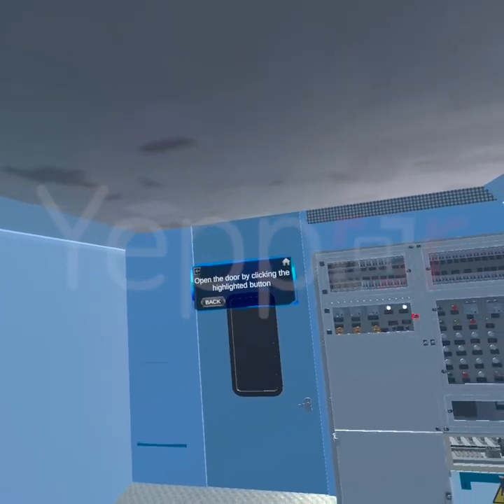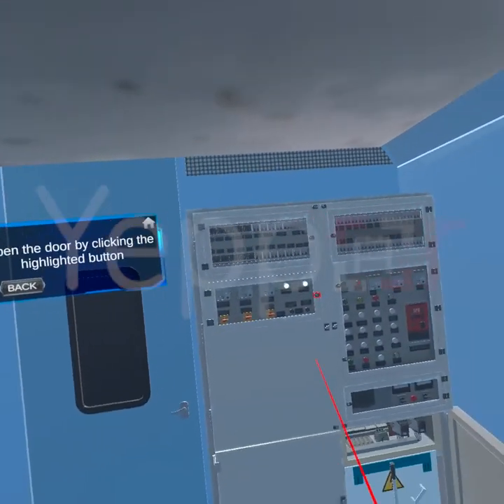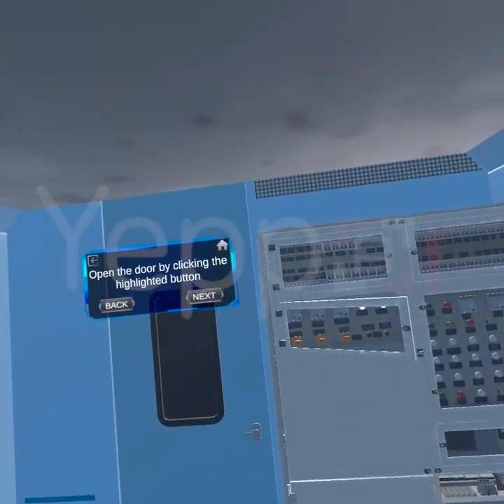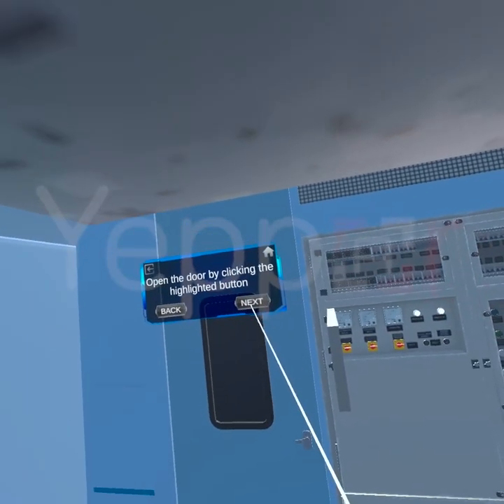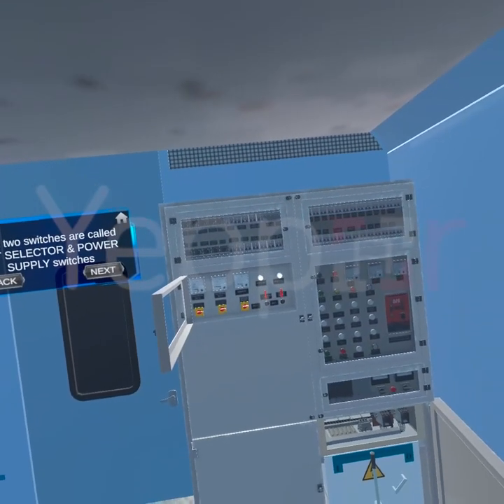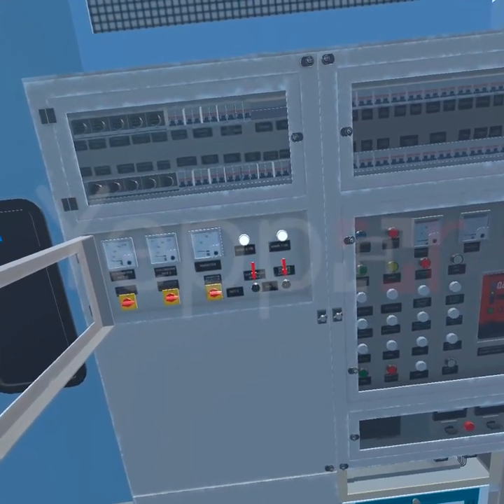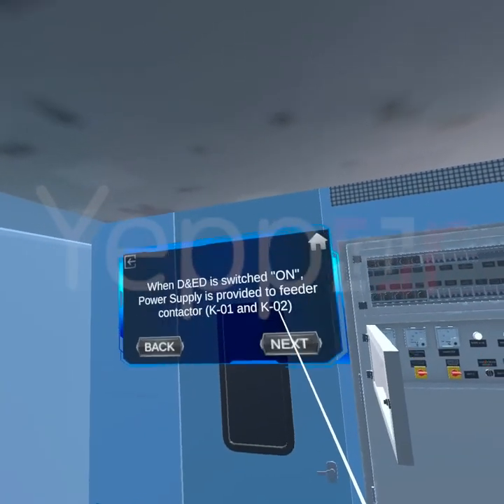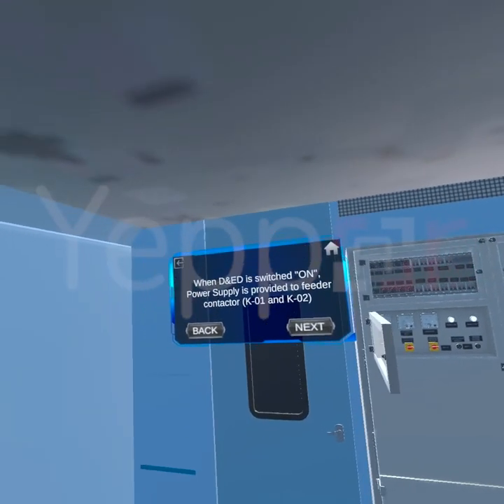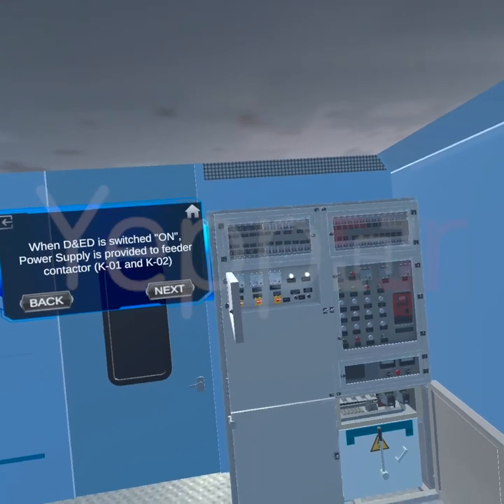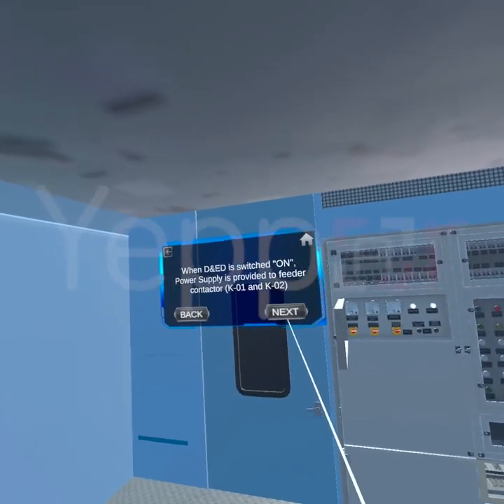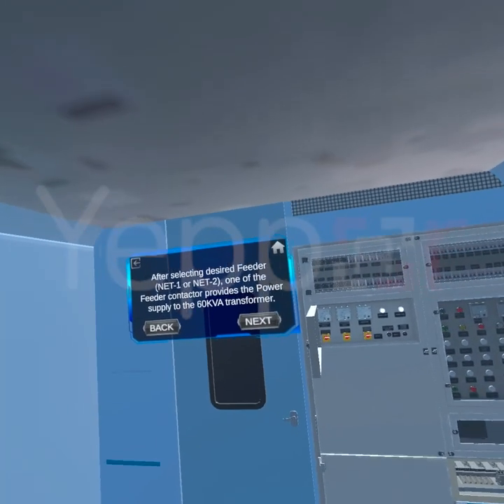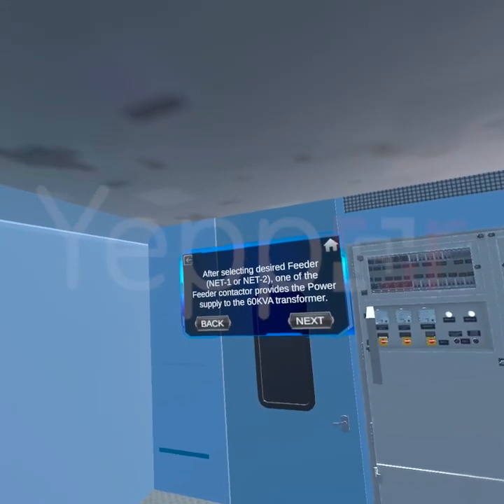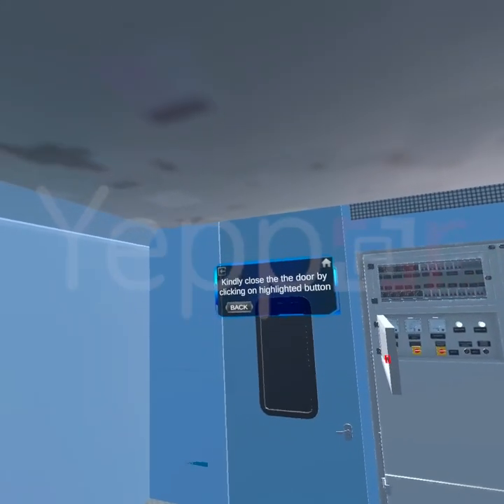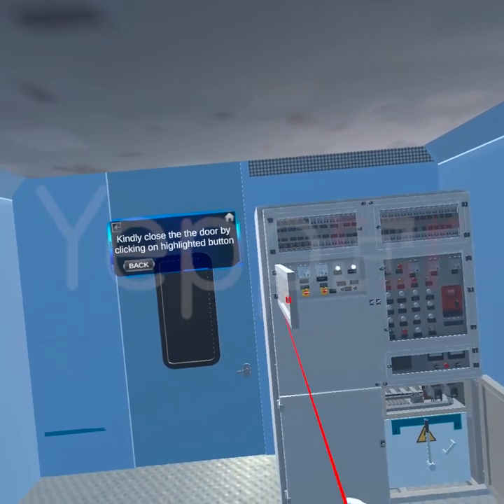Open the door by clicking the highlighted button. These two switches are called net selector power supply switches. When DED is switched on, power supply is provided to feeder contactor, K01 and K02. After selecting desired feeder, net 1 or net 2, one of the feeder contactors provides the power supply to the 60 kVA transformer. Kindly close the door by clicking on highlighted button.